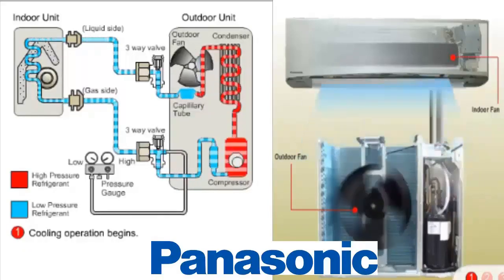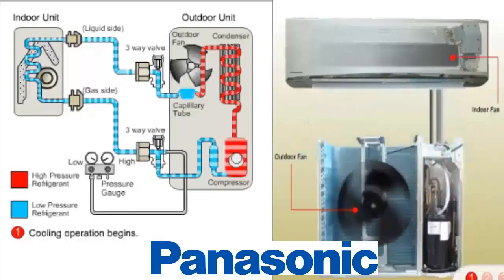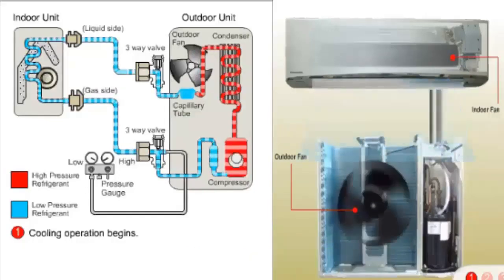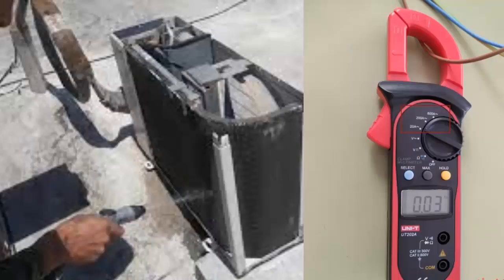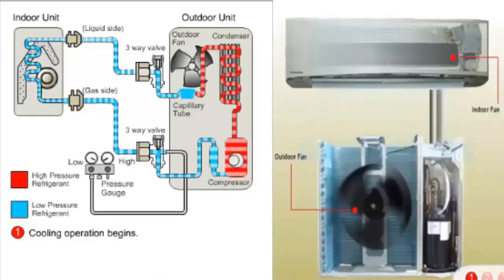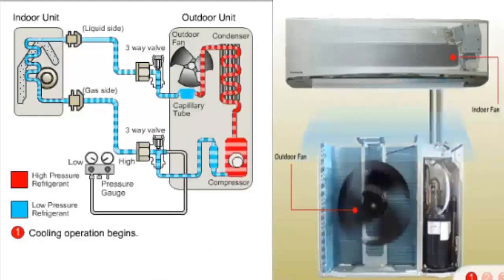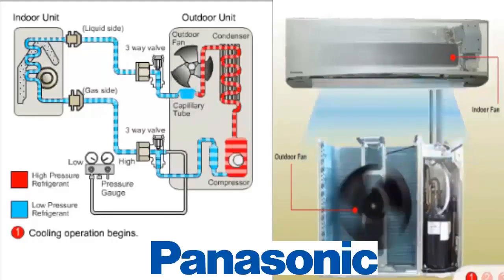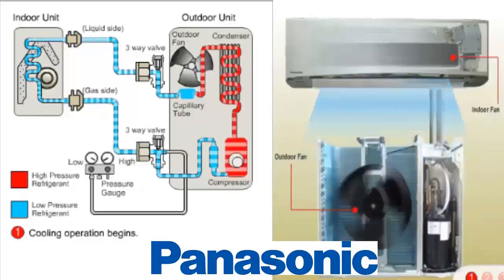1. If the ampere clamp value exceeds the nominal RLA value, but the equipment continues to operate, the first step should be to focus on cleaning the condenser or external unit of the equipment. Perform this external cleaning with water and soap. 2. Check the airflow of the condenser or external unit. If you observe low airflow, check the condition of the fan and test it with another capacitor.